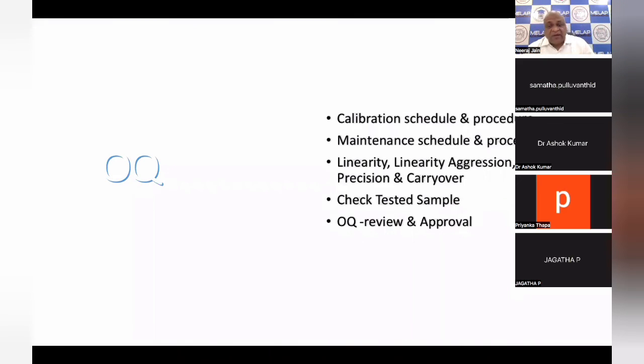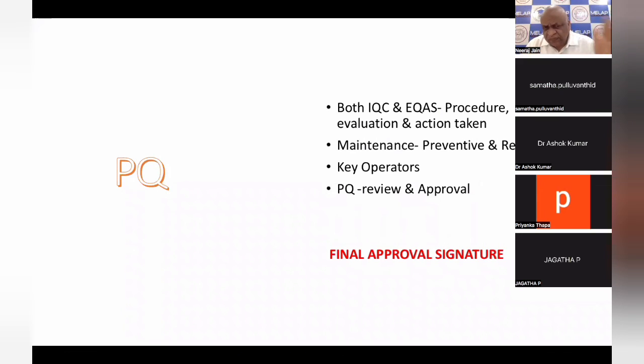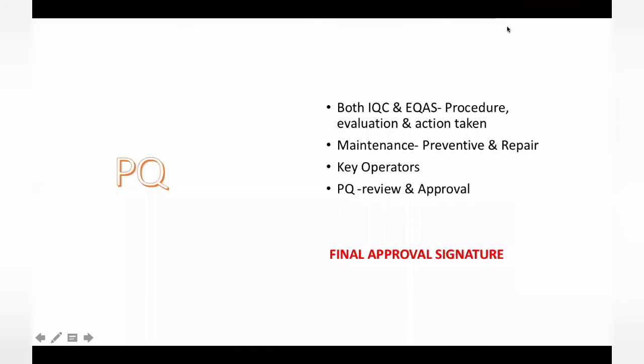After calibration, you are running controls, and control results are within acceptable limit. You are checking with already tested samples. If the results are comparable, you are saying, I have completed my operational qualification. Now your machine is ready for unknown samples to be tested. Now the machine is in regular use. You are participating in IQC and EQAS. For this, you shall have a documented procedure. This is the requirement of your clause 5.6 of ISO 15189.